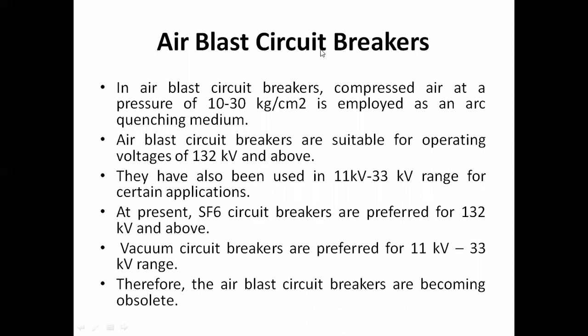Okay, now the air blast circuit breaker has certain advantages. Before we discuss the working principle of the circuit breaker, how it operates, there are certain advantages of the air blast circuit breaker. Now, what are the various advantages of the air blast circuit breaker over the oil circuit breaker? Number one, it is cheap, with free availability of the interrupting media, chemical stability, and inertness of the air. The reason being, it is very cheap, and it does not pollute the atmosphere, as well as it is freely available to interrupt the arc within the shortest possible time. So cheapness as well as free availability are the key advantages of this air blast circuit breaker.